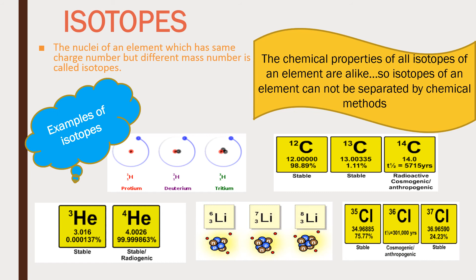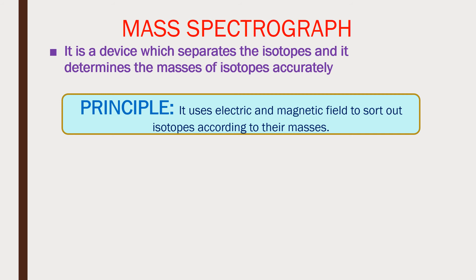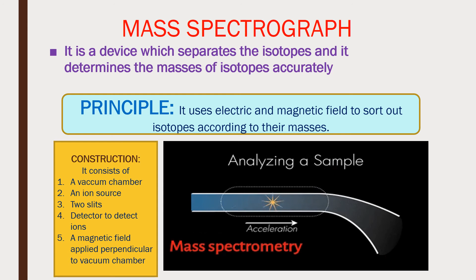A mass spectrograph is a device which separates not only the isotopes of an element, but also determines the masses of the isotopes accurately. Its working principle is that it uses electric and magnetic fields to sort out the isotopes according to their masses. It consists of a vacuum chamber, an ion source, two slits which are connected to the positive and negative terminals of the voltage source, a detector which is used to detect the ions, and a magnetic field B which is applied perpendicular to the vacuum chamber and out of the paper. The working of a spectrograph is shown in the figure.